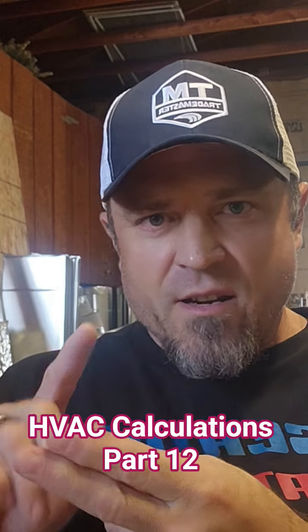Let's say you go in and Joe Homeowner did a remodel years ago that you didn't know about, and they got undersized duct in there. Your heat loss comes out to 100,000 BTUs, and he's got a supply trunk that could never handle that. If you do your Manual J and S and slap that equipment on there, the customer's not going to be happy. One, you're going to kill the equipment because it's going to short cycle. You're not going to get enough air across your heat exchanger. It's going to be noisy, like a wind tunnel effect through the duct.